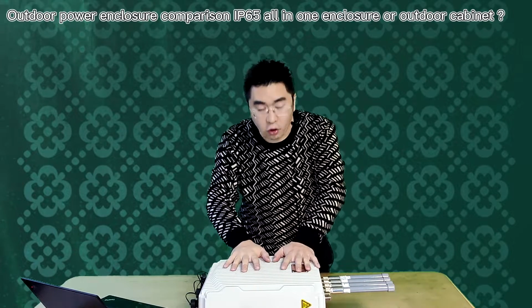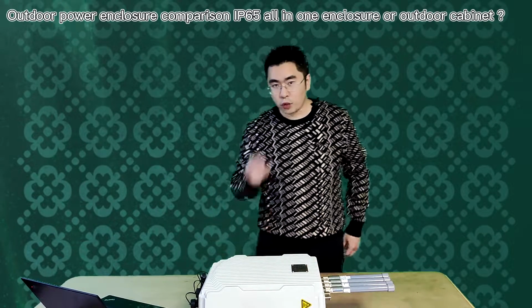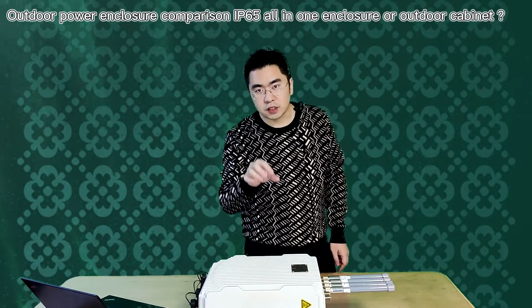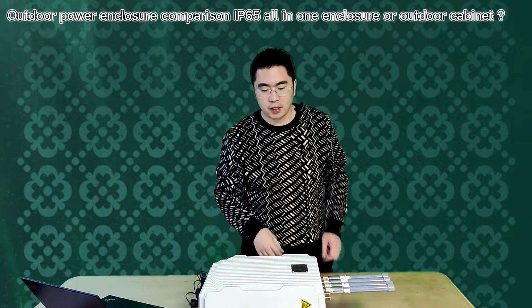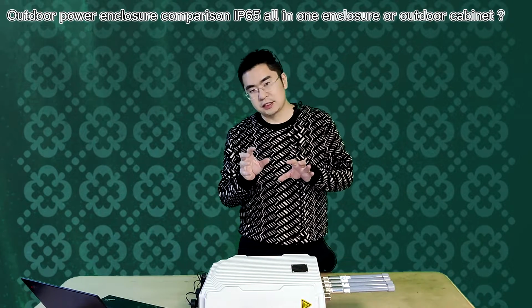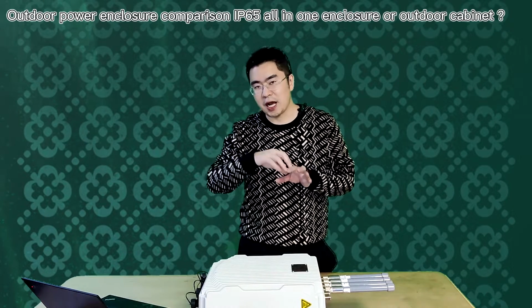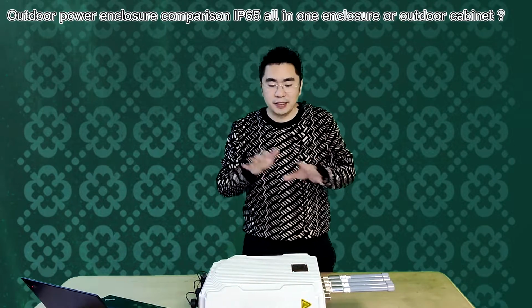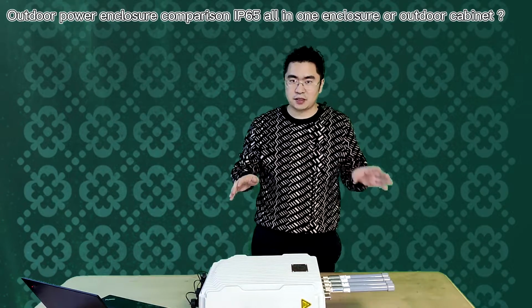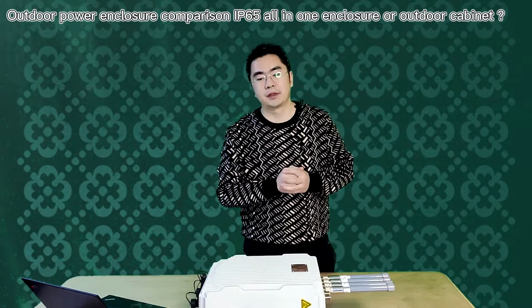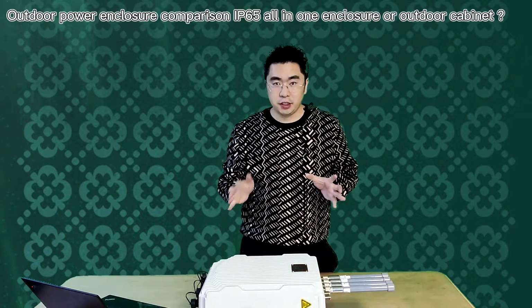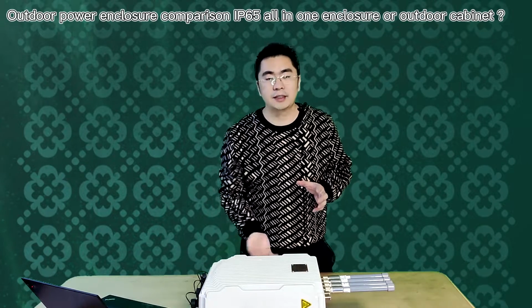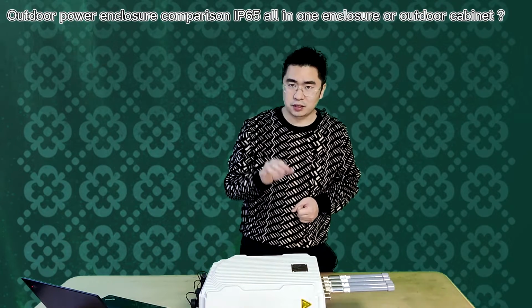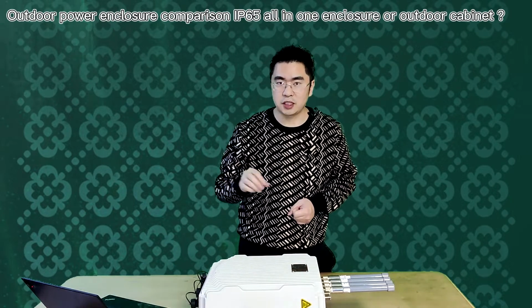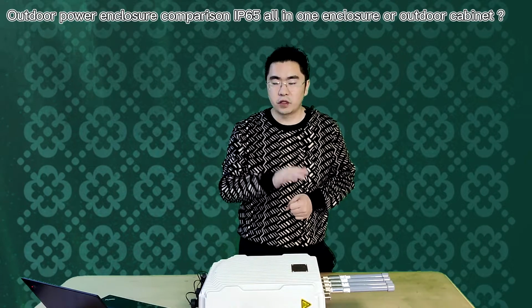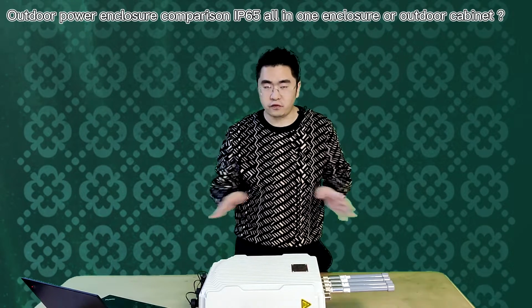If we use this kind of all-in-one design, we recommend using a lithium battery. Although the lithium battery's price is a bit higher than lead acid battery, in the end, from the capex plus opex, you save money, because lithium battery first can work longer than lead acid battery. Second, the working temperature range of this lithium battery is higher. 40 to 45 degrees centigrade is okay for them.